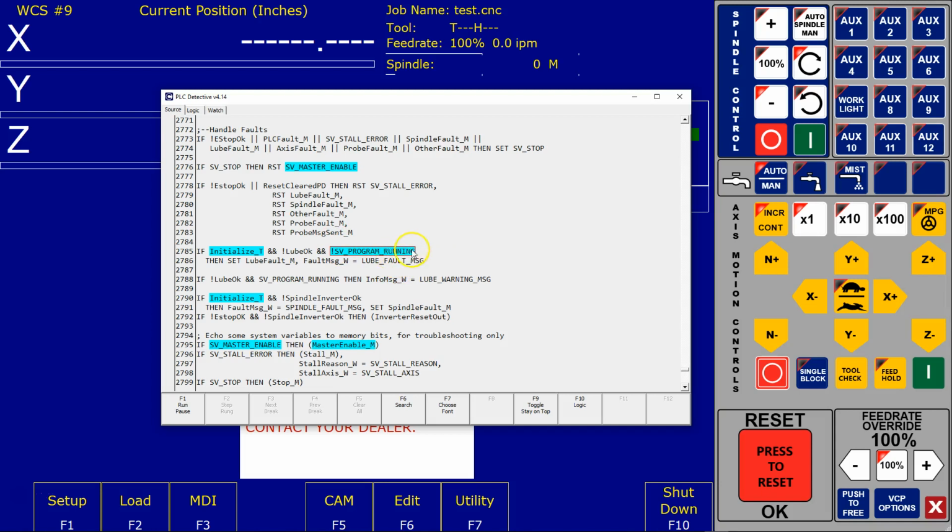Okay, here's one. On here there's essentially three conditions that need to be met in order to perform this outcome. And as you can see, the outcome isn't being set or turned on. In order to make that outcome turn on, this initialized timer is the one condition, and we see that that's in a true state.